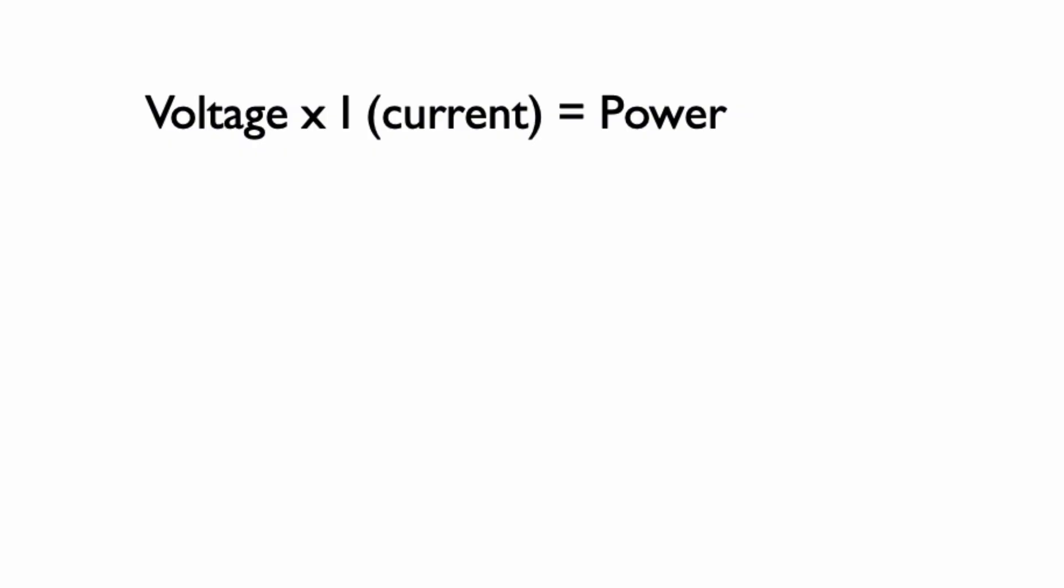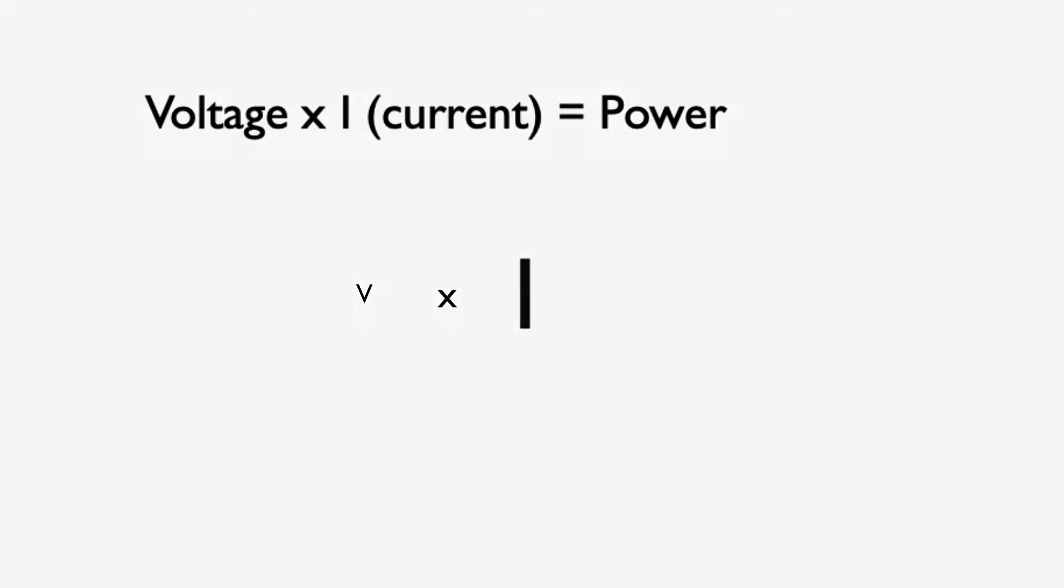In these designs it's always best to keep all the calculations in total power units and not convert it into current. The devices that are run off of the 48 volt bus are constant power devices because they use DC to DC converters. A constant power device implies at any given power level as the voltage goes up the current goes down and when the voltage goes down the current goes up such that the product is always constant and hence constant power.